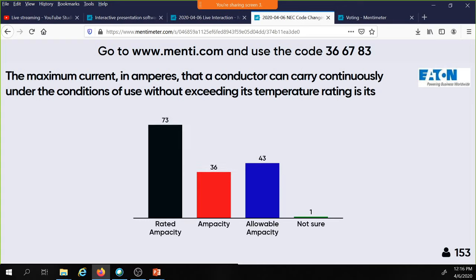Well, I like this question because I chaired a task group that sought to clarify this. And what we decided as a task group is that rated ampacity does not belong in the National Electrical Code, because it's not rated ampacity. Ampacity is always the amount of current that can be handled based upon its conditions of use. It's not a rating, and it's also not an allowable ampacity. It's just pure ampacity. So one of the changes we made globally, based on a task group I chaired, appointed from the correlating committee, we went through the National Electrical Code.